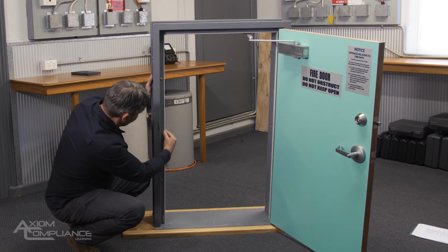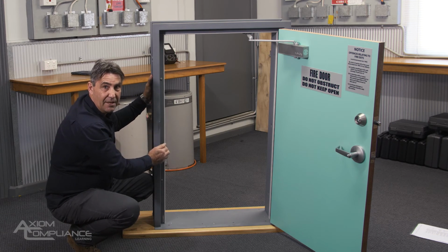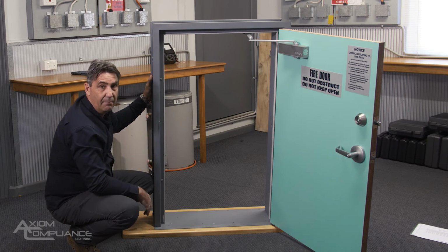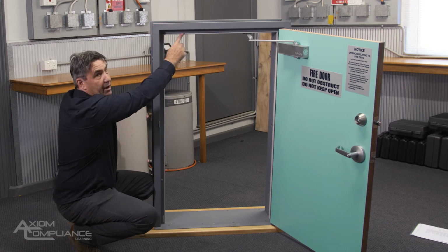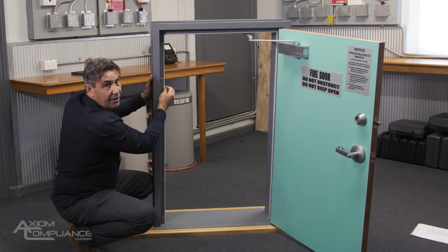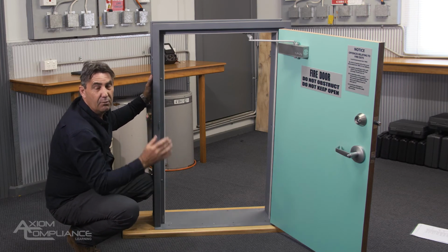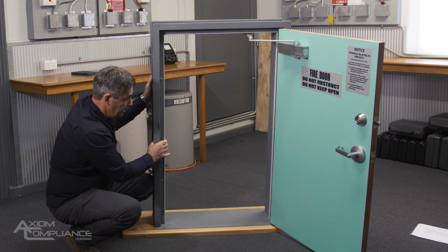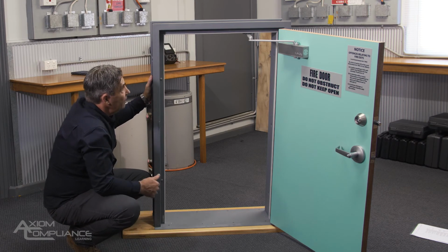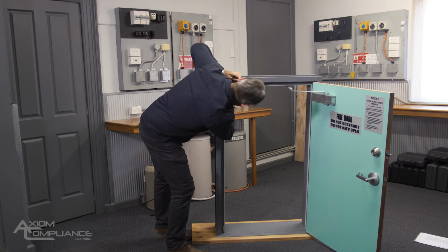And we can also see around the edge of it, and oftentimes these fire door seals are put in place right from the installation time. These seals have got to be inspected to make sure they don't have any gaps or breaks or holes in them. It's also a good idea to slide them up and down and see whether they're moving or not. And once again, it's a piece of hardware. We've got to make sure that this is actually a fire rated seal and it's meant to go on this particular door set. Okay? So when you're inspecting your frame, just look around all of the joins.